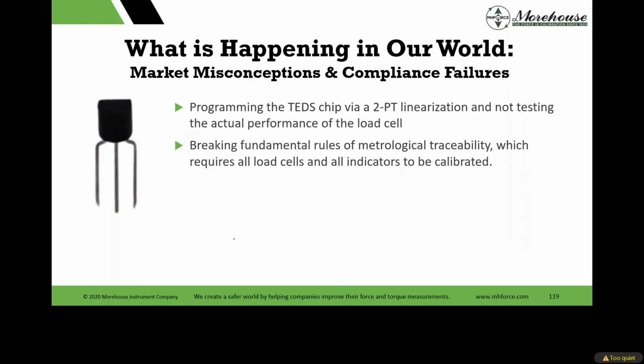The reason I'm biased against TEDS is this technology was invented around 2000. It's an IEEE standard. And then it's all this Industry 4.0, and they have these buzzwords and terms. Create smart, interconnected manufacturing systems that leverage automation, real-time data, artificial intelligence to optimize efficiency, flexibility, and decision making. And what happens is some salesman somewhere sells somebody a load cell with these TEDS chips, and it sounds like the greatest thing in the world. And what ends up happening is the accreditation body or the person that comes to your site, if you're accredited, they determine that you're breaking all of these rules on metrological traceability that require the documented chain of calibrations, each contributing to measurement uncertainty.